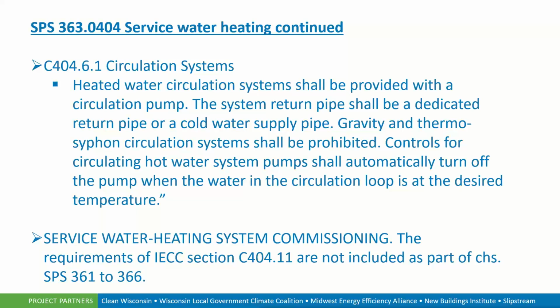Moving on a little bit further in the code, we talk about circulation systems. Again, there is the section of the code that the heated water circulation system should be provided with a circulation pump, obviously, and it goes on to further define what that circulation system is. But there's also a portion of the IECC 2015 code that was amended or deleted. C404.11 is not part of the code. Again, be careful when you're looking at service hot water system commissioning, and that's again not required to be completed as part of the current code.